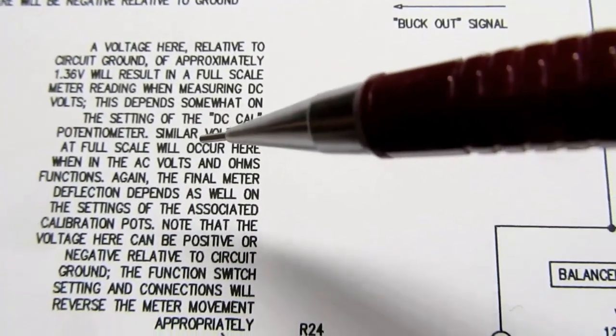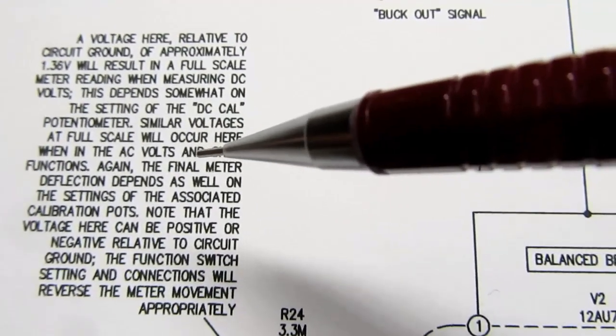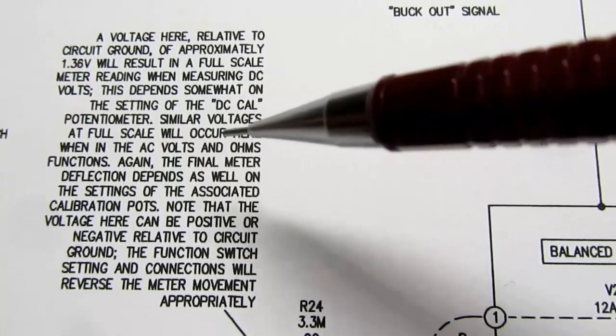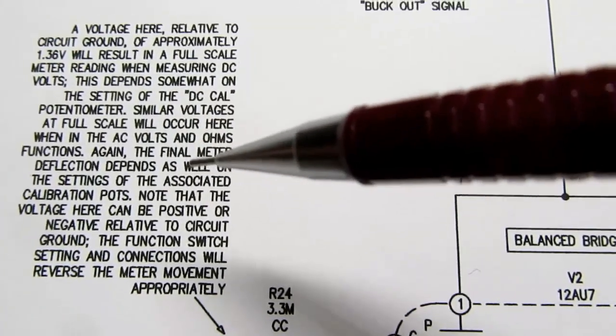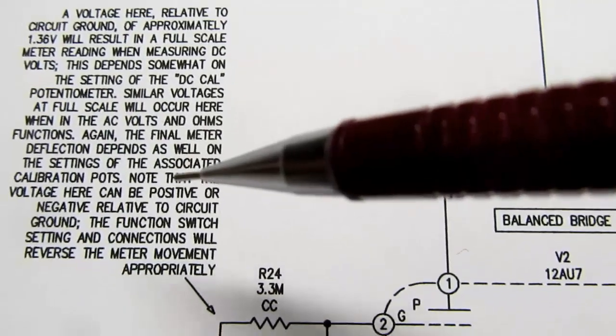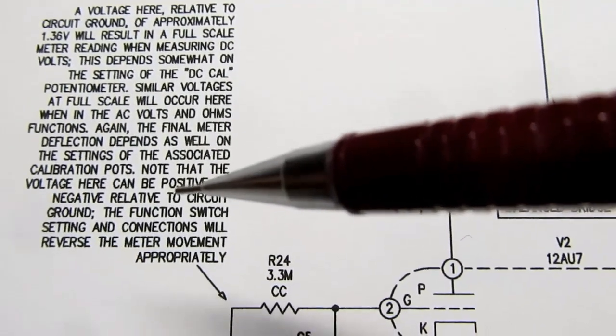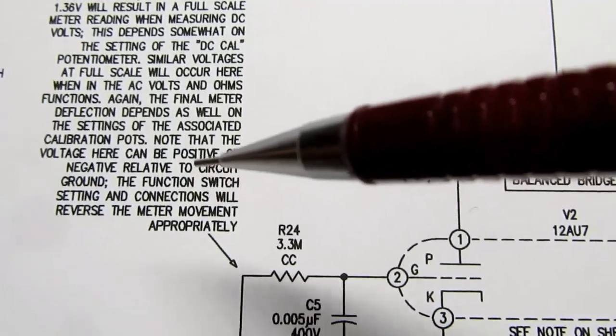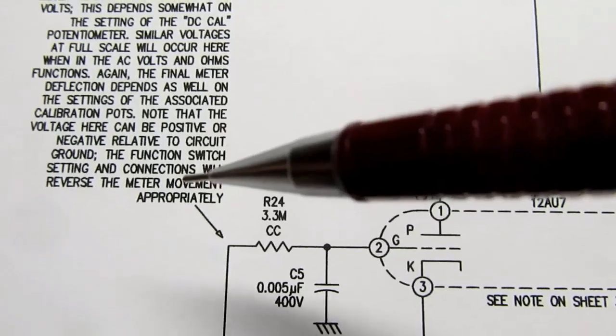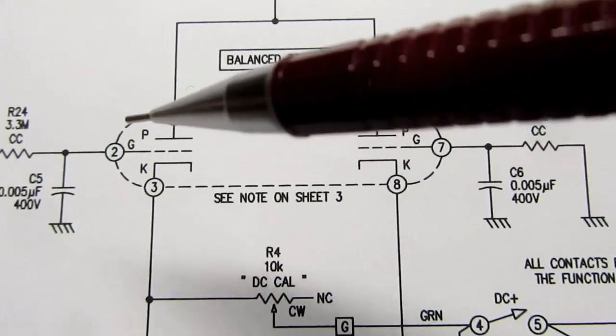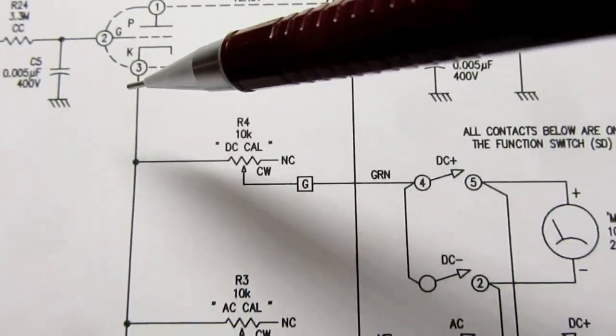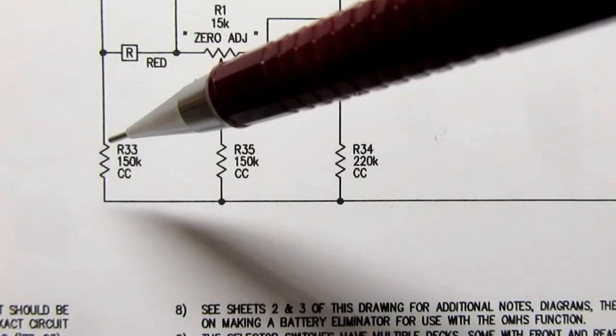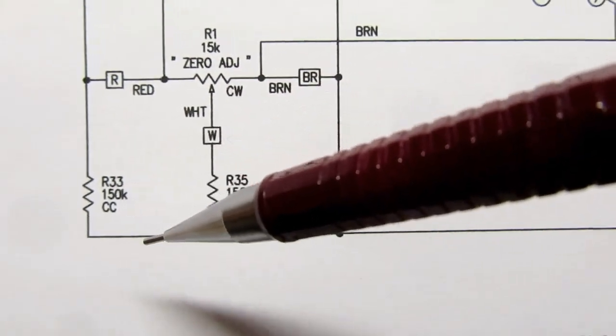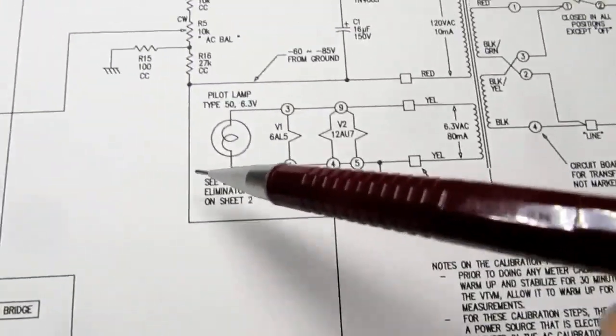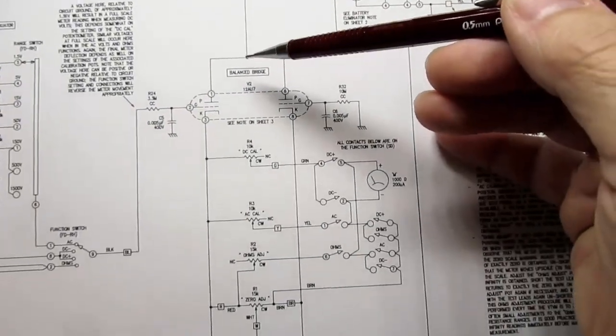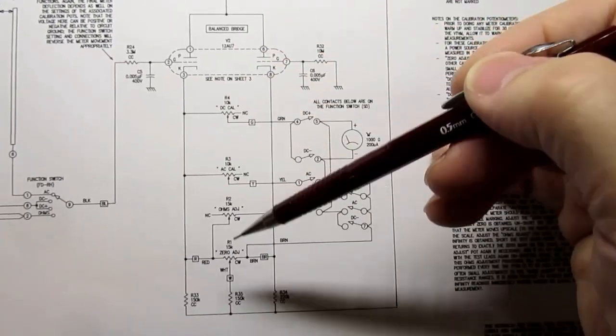And of course the full-scale reading depends on the setting of the DC cal potentiometer, which is further down in the circuit. Similar voltages at full scale will occur here when in AC volts and ohms. The final meter deflection depends as well on the settings of the associated calibration pots. Note that the voltage here can be positive or negative relative to circuit ground. Anyway, so then the current continues down through here and through this 150K resistor back to this point, which is V minus.